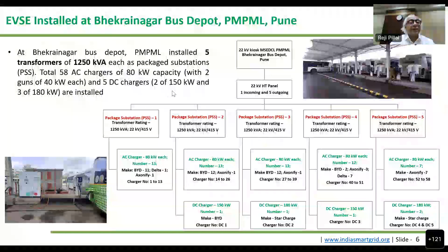What we did in Pune, Bhekrainagar, as I said, is they have taken a 22 kV connection from MSEDCL, and the 22 kV panel in the bus depot has 5 outgoings, each going to a separate package substation, with 1250 kVA, 22 kV by 415 volt substations, from where they connect to different numbers of chargers. There are 5 DC chargers and 58 AC chargers of 80 kilowatt capacity, each with 2 guns of 40 kilowatt. This is what existed there when we conducted the study.